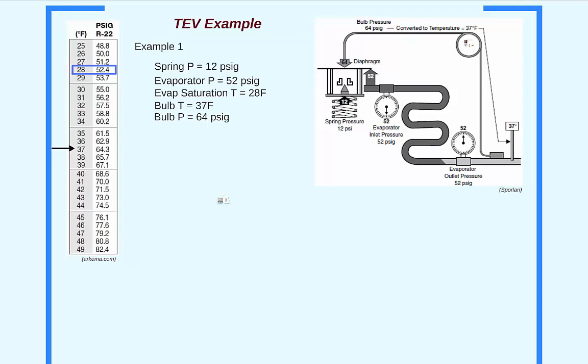The valve diaphragm is experiencing a 64 psi opening force from the bulb and a 52 plus 12 psi closing force from the evaporator and spring. The valve is balanced because both sides exert a 64 psi force. Superheat is determined by taking the difference between the sensed bulb temperature and the evaporator saturation temperature. Subtracting 28 degrees from 37 degrees gives a superheat of 9 degrees for this cycle.